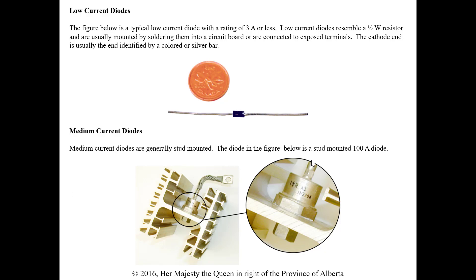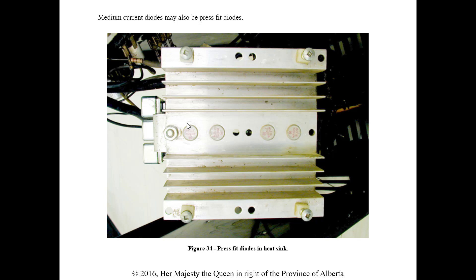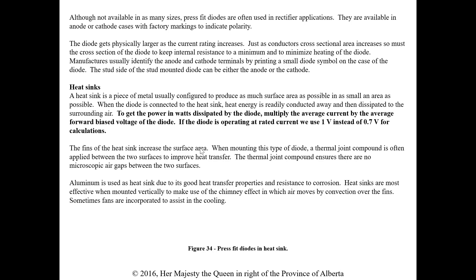Medium current diodes are usually stud-mounted. The one in the figure is a stud-mounted 100-amp diode. We do have these in our battery chargers. There's a heat sink it's mounted onto to help dissipate heat. They can also be press-fit diodes, pressed right onto a heat sink to dissipate heat from the diode, since current going through them creates a lot of heat. The diode gets physically larger as the current rating increases — just as a conductor's cross-sectional area increases, so must the diode's, to keep internal resistance to a minimum. Manufacturers usually identify anode and cathode terminals by printing a small diode symbol on the case. The stud side of a stud-mounted diode can be either anode or cathode, so watch that when installing.